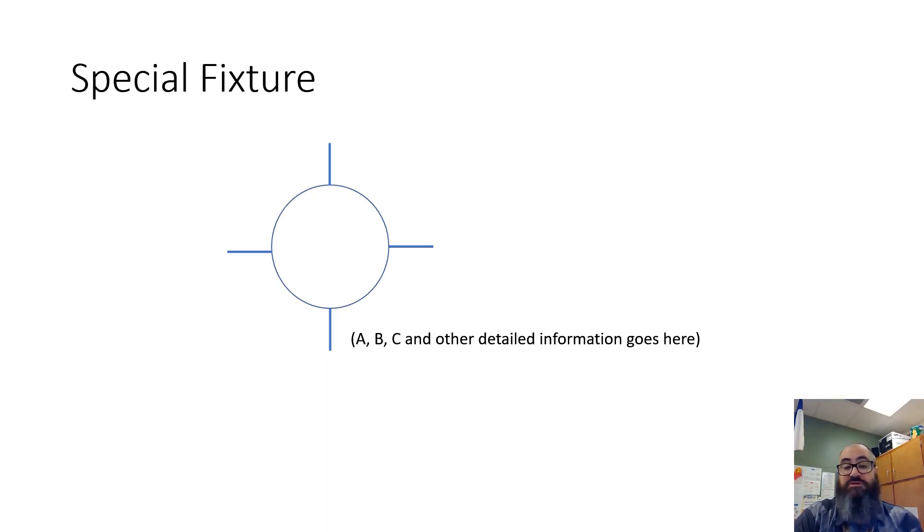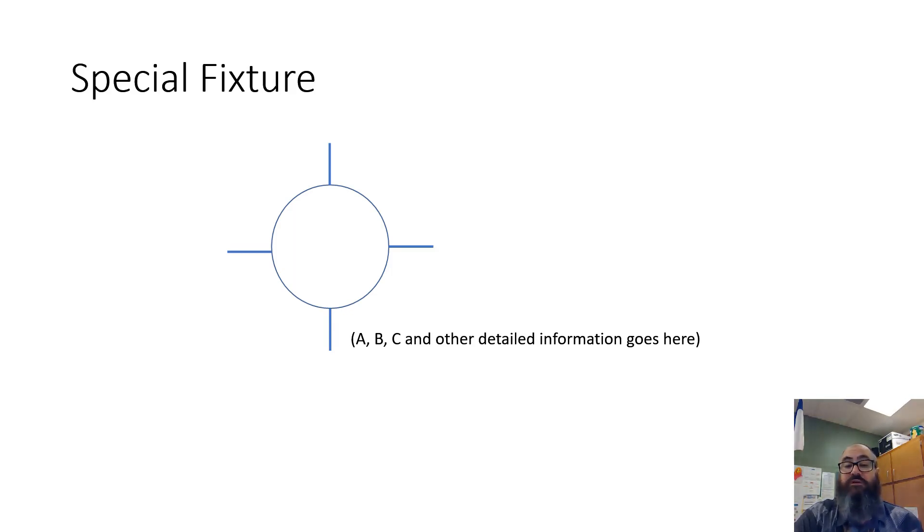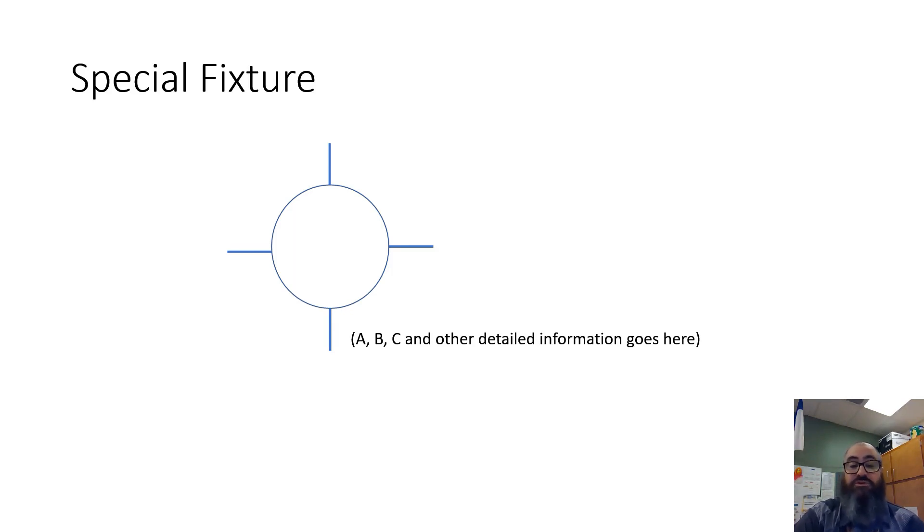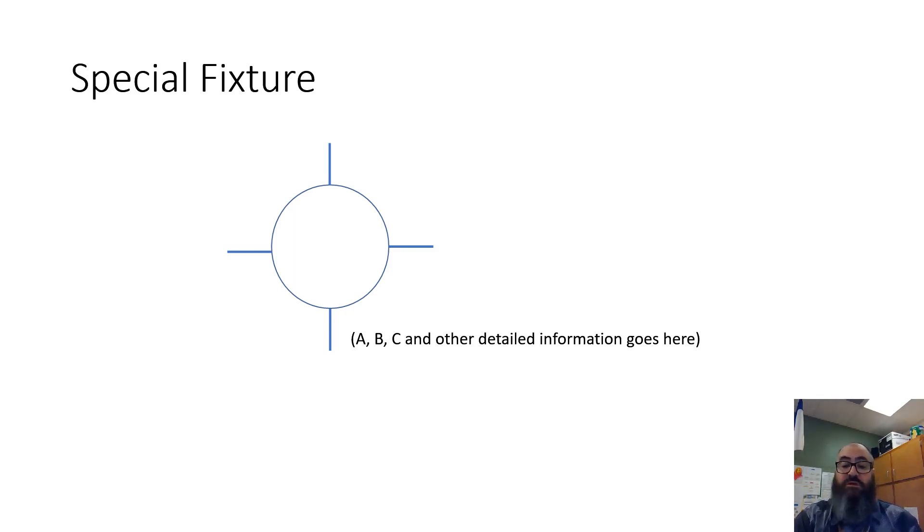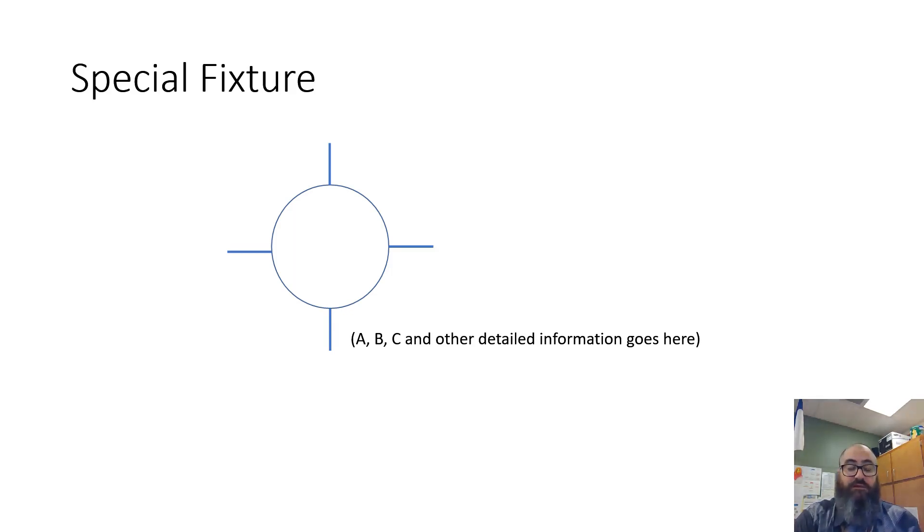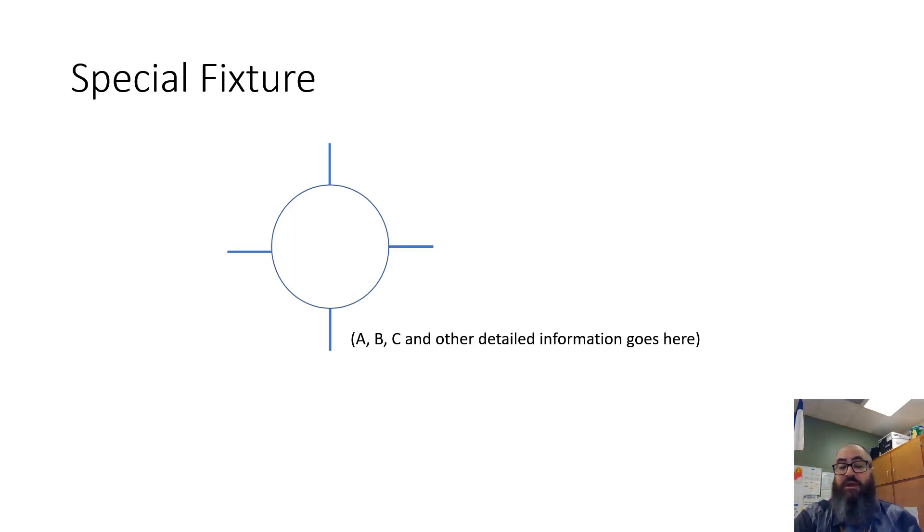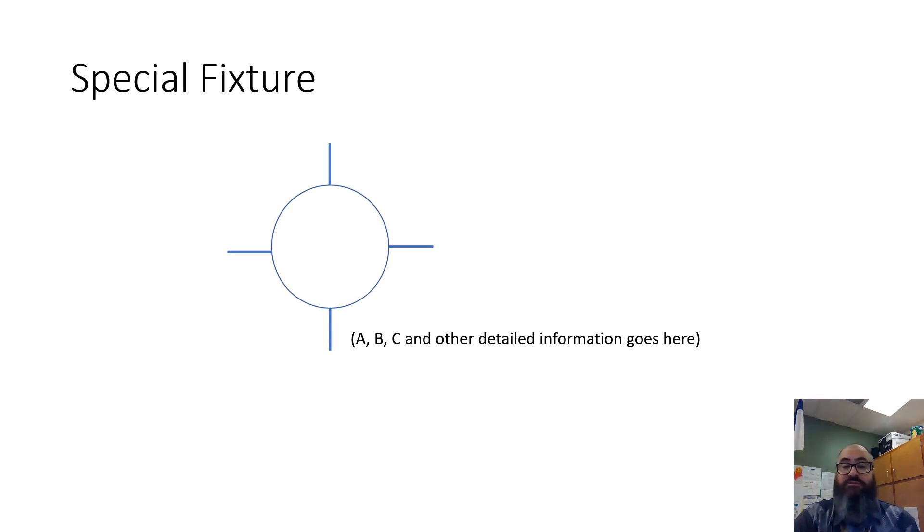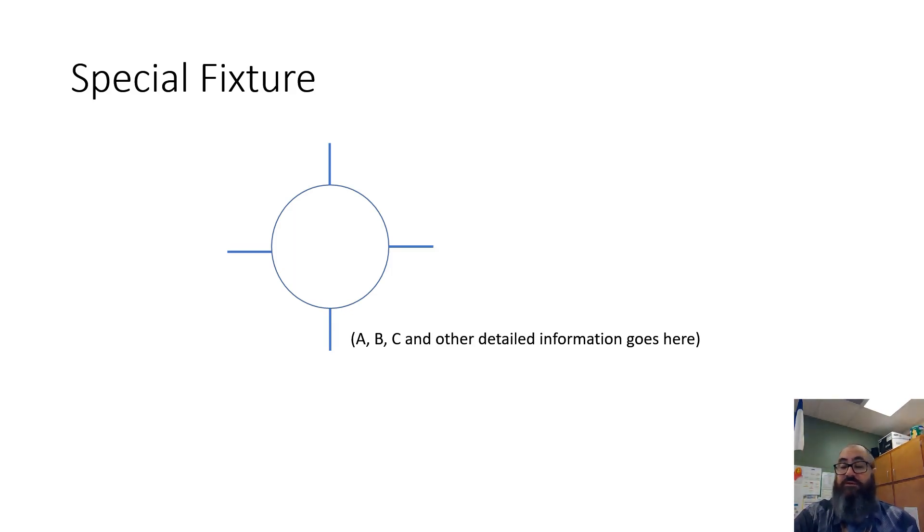Special fixture. Basically the same symbol as a surface mount fixture, however you will have notes beside it explaining any additional information regarding that fixture. It could be a heat lamp or maybe some sort of special lighting for a special lighting effect. Anything that really doesn't have a definite symbol, you would use this but with notes beside it. Typically a lot of them will have notes, not necessarily always beside them but in a legend somewhere or a schedule on a set of plans showing what that symbol represents in more detail.